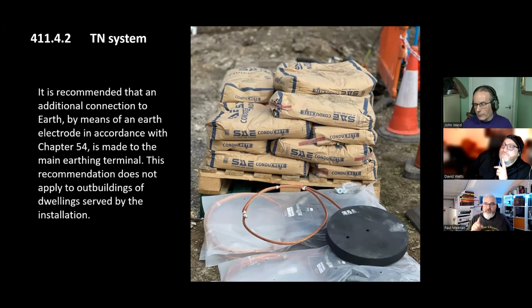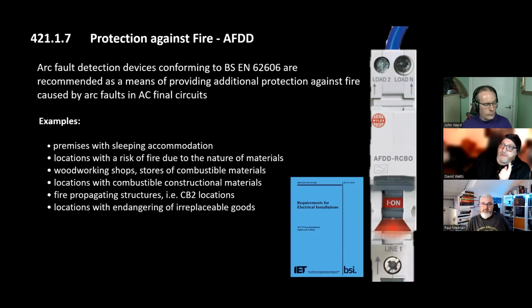And that makes it very difficult when we're prosuming, which John and I will talk about later on, and we're doing switching of earths and everything else. So this is good in one breath, but if you put this electrode in and you start getting current flowing down it, then it's masking the hazardous effects of a broken PEN. That's really dangerous. Now, it's good for the networks because it means they save money. So I'm not a fan of this regulation in that context, but we will move on. I'm a fan of it as an electrode for island mode, but not in the context of it covering up this other issue. Very good point, sir.